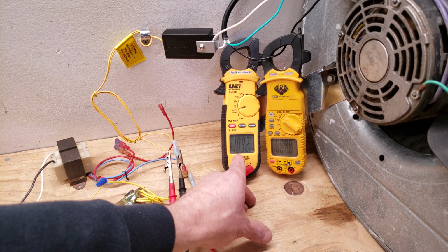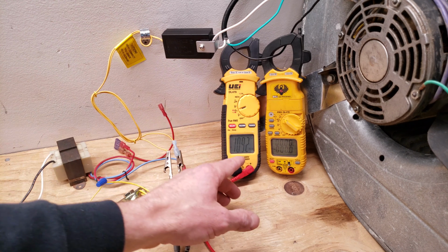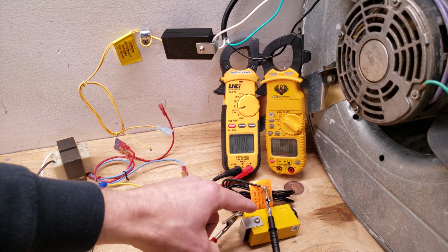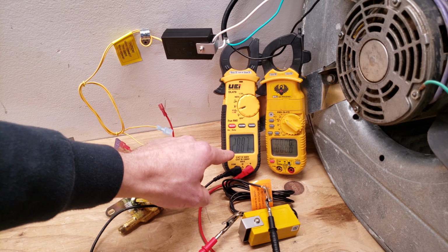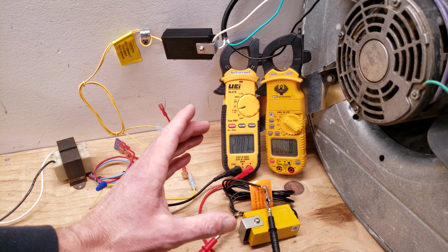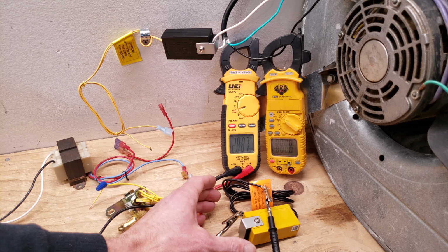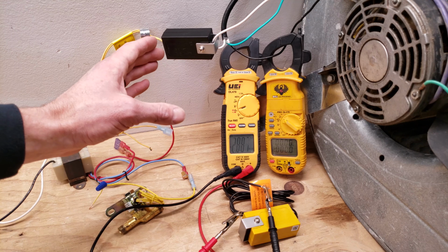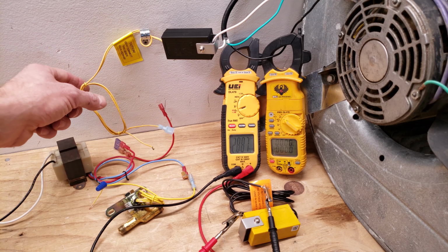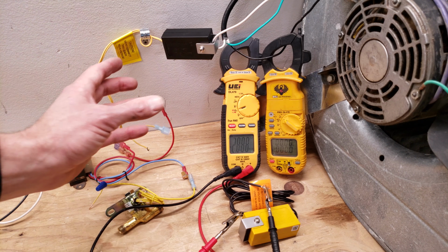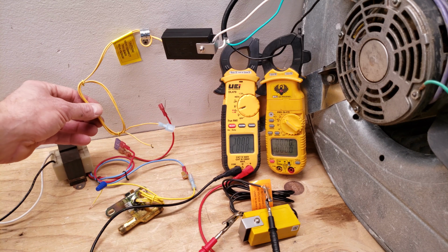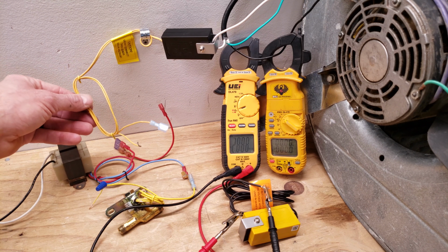However, it does not read OL when it's open. It does read in mega ohms. This 120 volt current sensing relay reads 2.8 mega ohms. So if the power's off, you're going to read mega ohms. Now in reference to troubleshooting these, you can't do it with the 24 volts off of it. So even if you're drawing amperage over here, you have to also have 24 volts entering this.